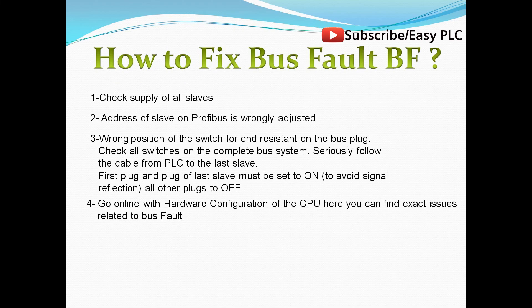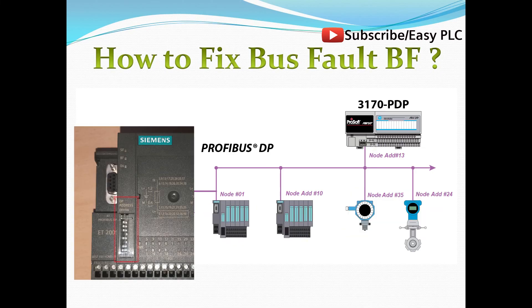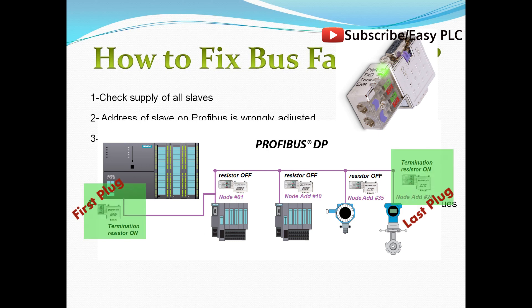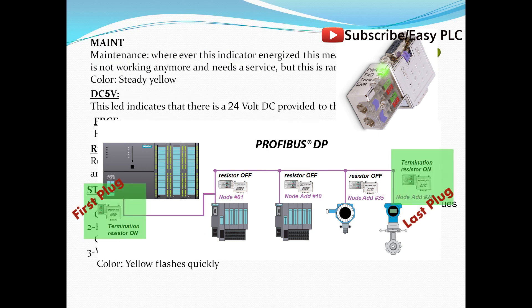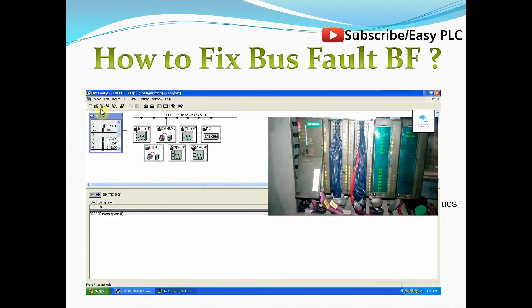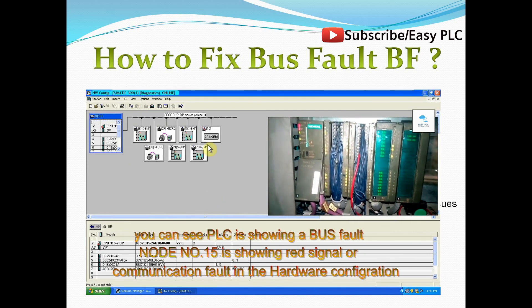How to fix bus fault? Check the supply of all slaves. Verify that the address of each slave on Profibus is correctly adjusted. Check the position of the switch for end resistor on the bus plug. Check all switches on the complete bus system and trace the cable from the PLC to the last slave — the first plug and plug of the last slave must be set on, and all other plugs set to off. Go online with the hardware configuration of the CPU to find exact issues related to the bus fault.